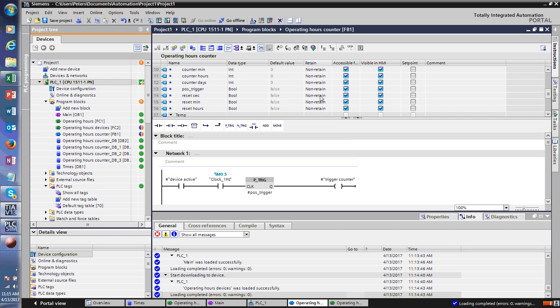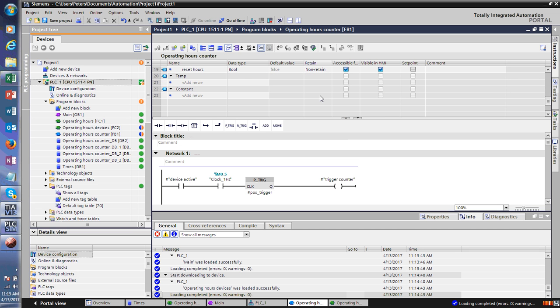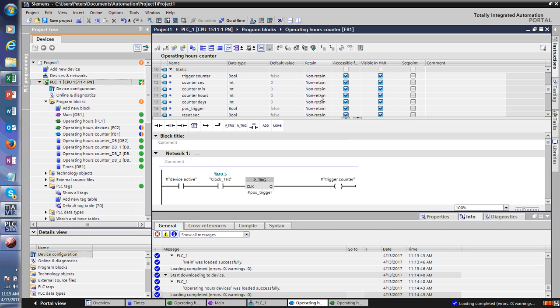So what else do we need? We need to have the counters retain, otherwise it will start from 0 and move your zeros or whatever in your output. And even if your output is retained, it will override it. So you put all that to retain and you should be good.